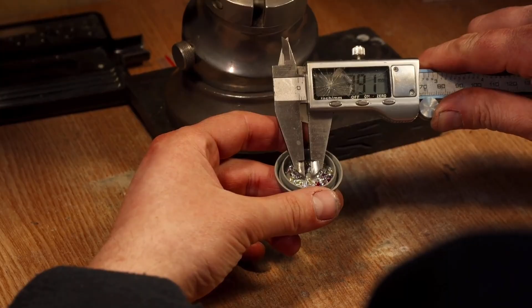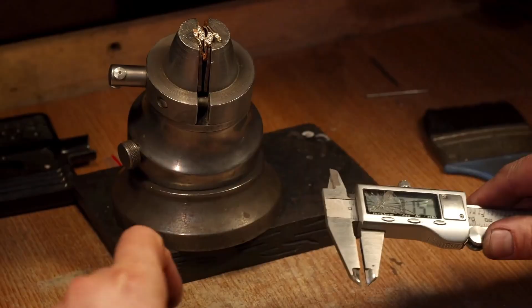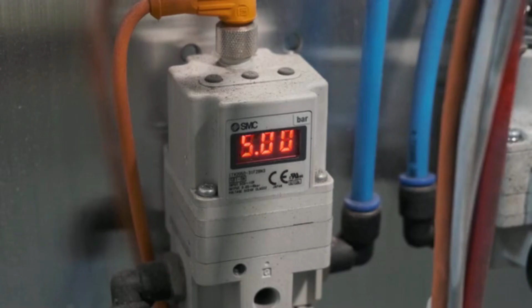Now, from where will you do the calibration? You need to do the calibration from the competent authority. Who is the competent authority? That is a NABL certified laboratory or NABL certified agencies. I cannot take my instrument and give it to anyone to do the calibration. It is not accepted. NABL has given the agency the authority to do the instrument calibration. So before doing the calibration, you need to check that this agency is NABL approved or not. If not, we are not going to that agency, because your result will be erroneous and your calibration report will not be accepted. So first you need to check that the agency we are choosing for calibration is NABL certified and certified to do the calibration. This is the first part you need to do.